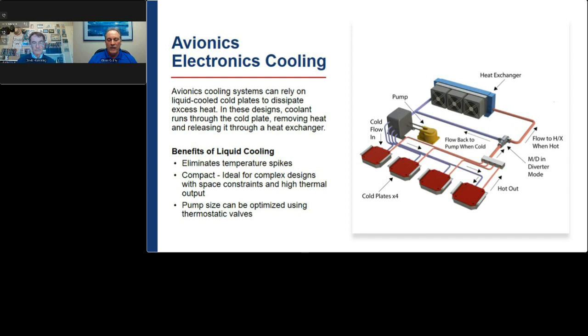When it gets into the range where the optimal temperature of the equipment needs to be, it then modulates the spool, as we had said previously, and now goes up through the heat exchanger. And again, it could always be somewhat open. It's not an either or. With the modulating bypass type valves, they can actually control any intermediate temperatures that are not quite cold enough or not quite hot enough. But when it's in the totally cold scenario, it will bypass 100% to the cold. And if it's totally hot over the range, it'll bypass everything through the heat exchanger.